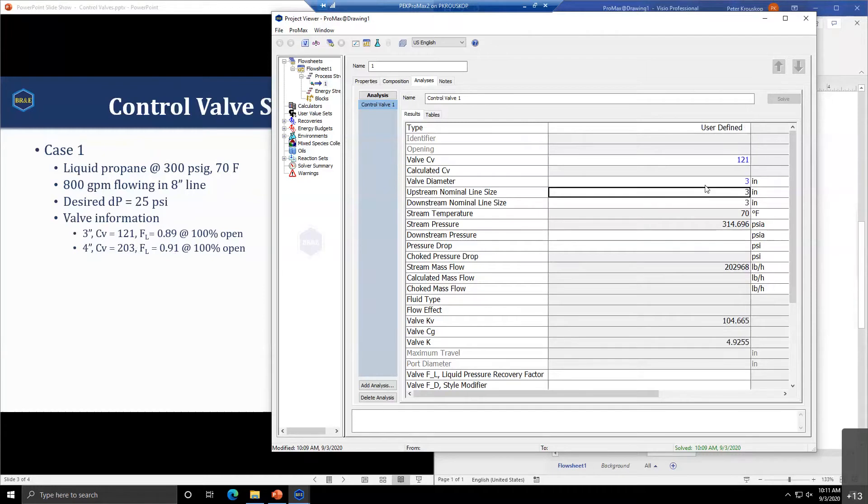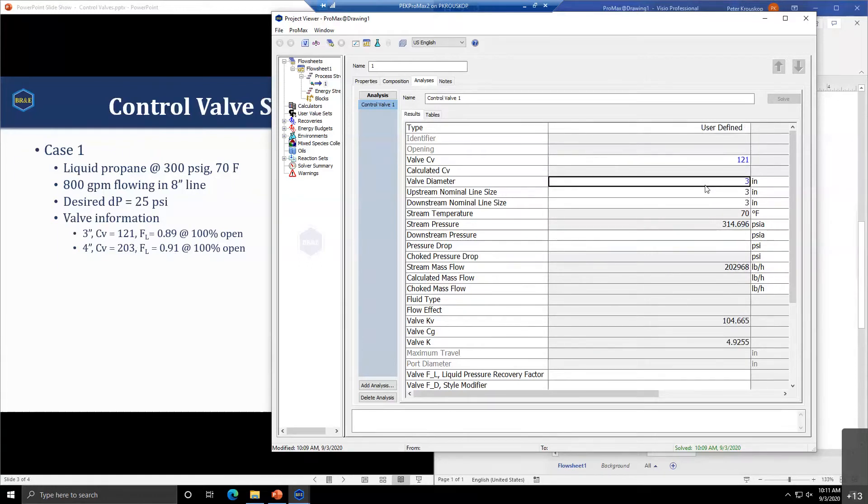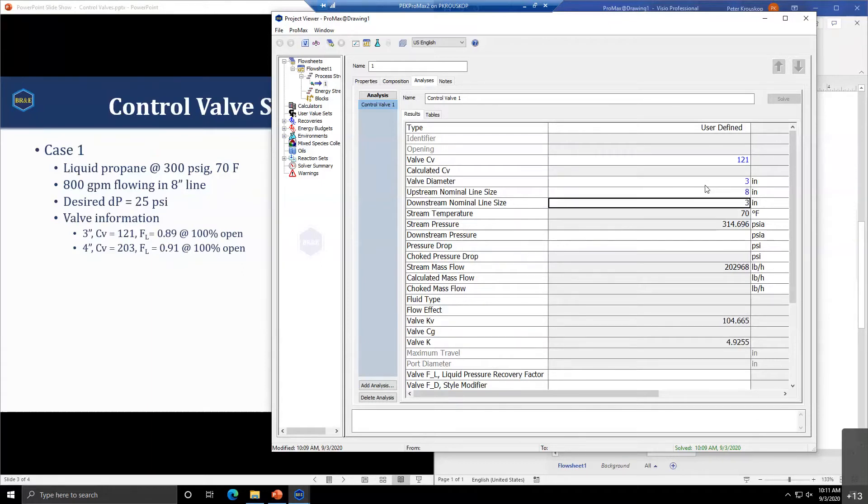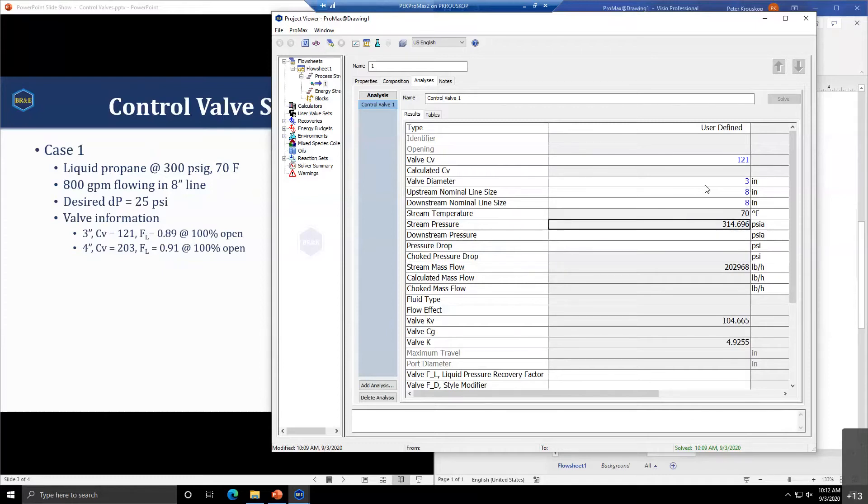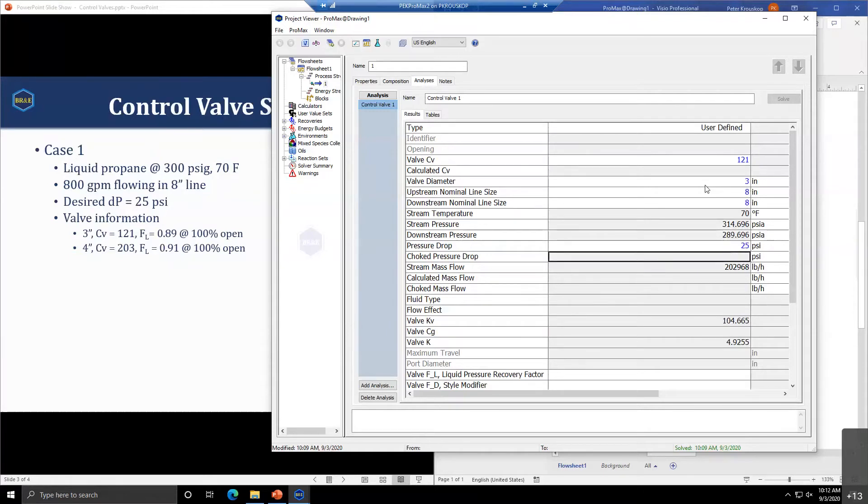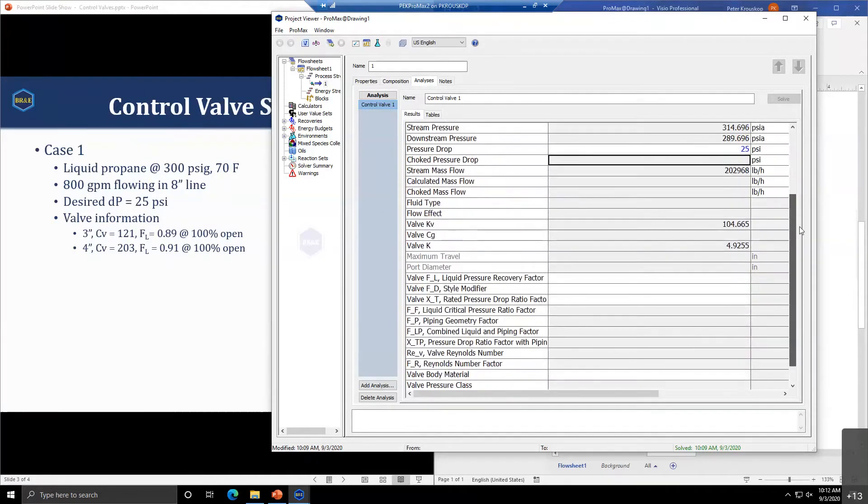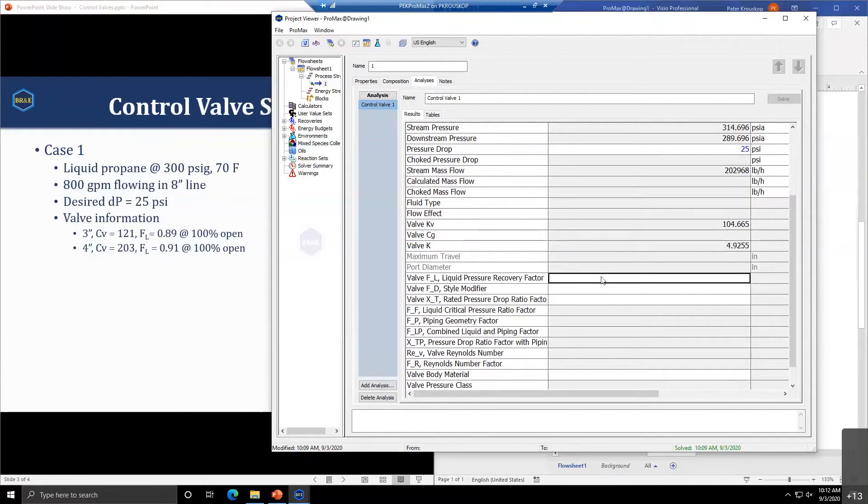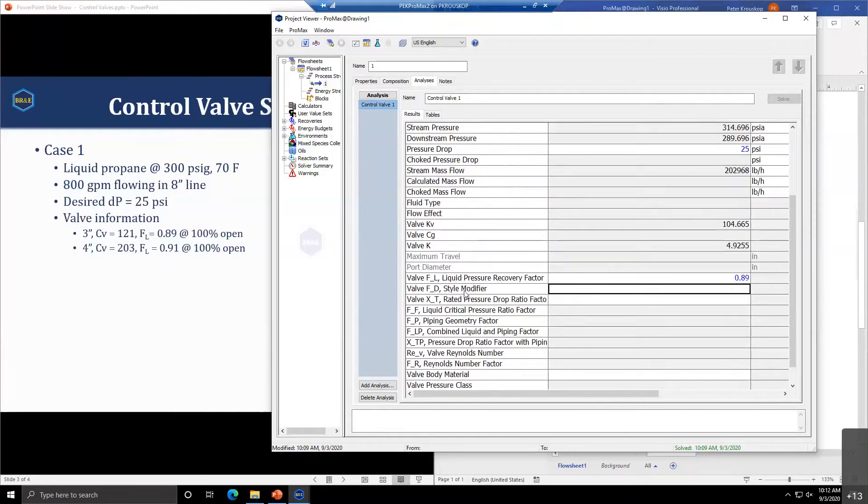Our valve diameter is three inches. The upstream pipe is 8 inches. By default, ProMax assumes the upstream and downstream line sizes are the same size as the valve diameter. In this particular case, that's not what happens, so we need to change that.